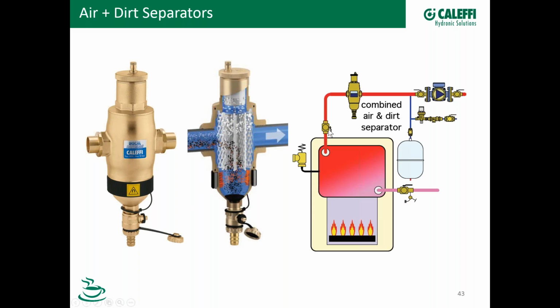So where do we locate that? Well, we're showing it in this schematic, again, in the hot pipe right here. Now, we get that question, well, if I have a combo unit, do I put it here where the temperature is the highest, or maybe I should put it back here on the return to the boiler so I eliminate the dirt before it gets into the boiler? Well, it's our general opinion that the temperature trumps the dirt removal. Why? The air, it's extremely important to get the air out for reasons of corrosion and everything else that happens downstream. Now, we'll pull the dirt out right here, that's true, but that dirt has already passed through here. But if it were me, if I had to make the call, I would say put it on the high temperature pipe.